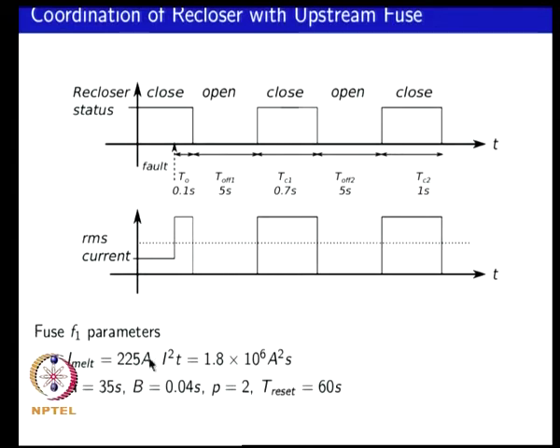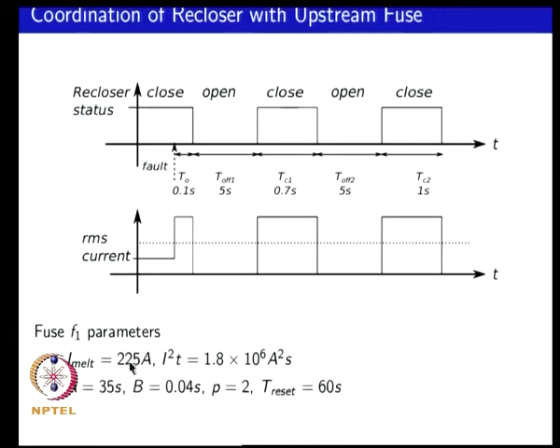For the upstream fuse, we assume a melt current of 225 amps. The I²T is 1.8×10⁶ ampere-squared seconds, and the fuse needs at least 2 cycles (40 milliseconds) to operate. It has an extremely inverse characteristic with P=2, giving A=35, and a reset time (cool-down time) of 60 seconds — meaning after it gets fully hot, after one minute the fuse cools back to nominal temperature.